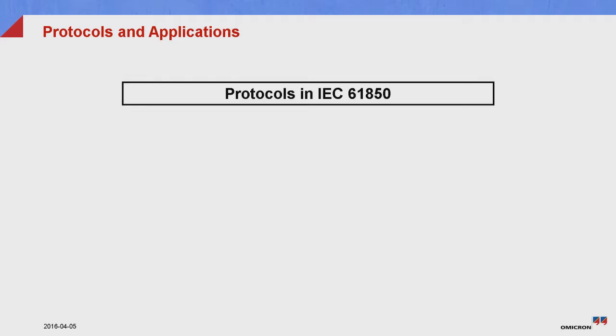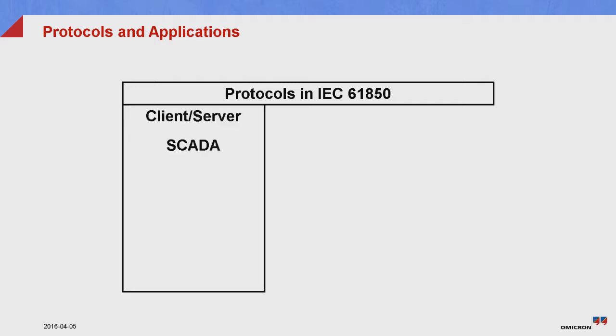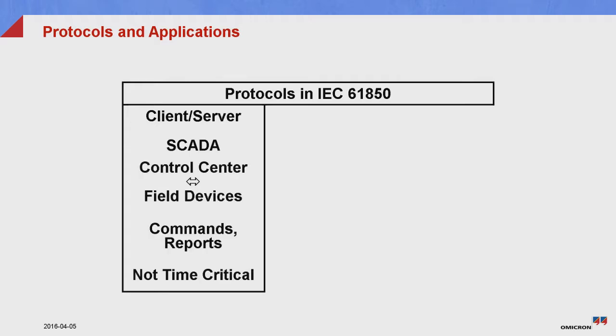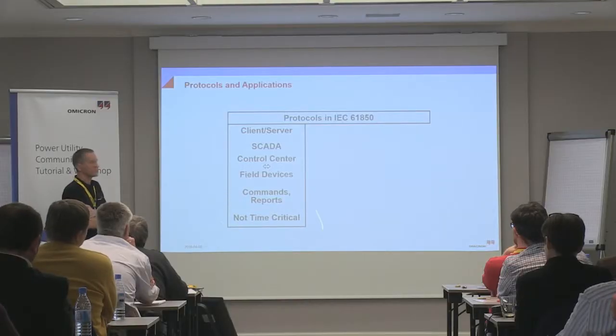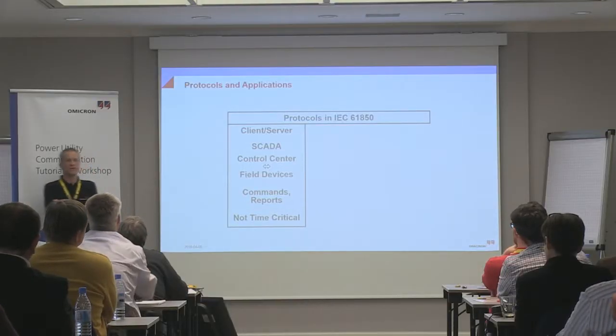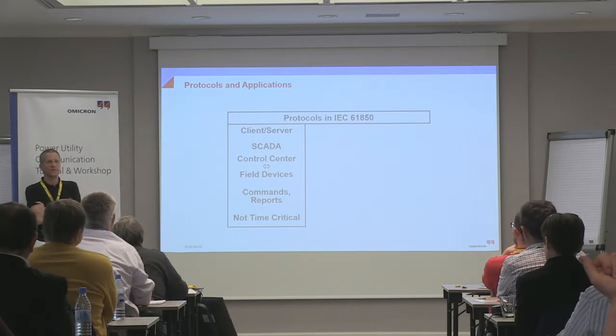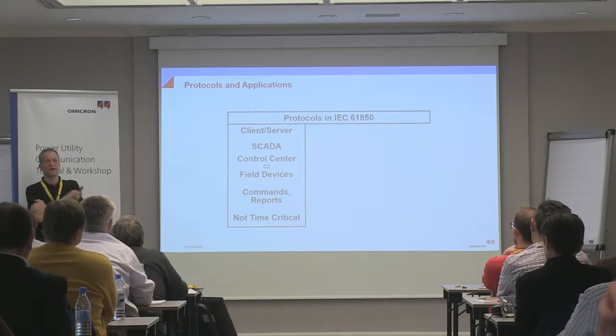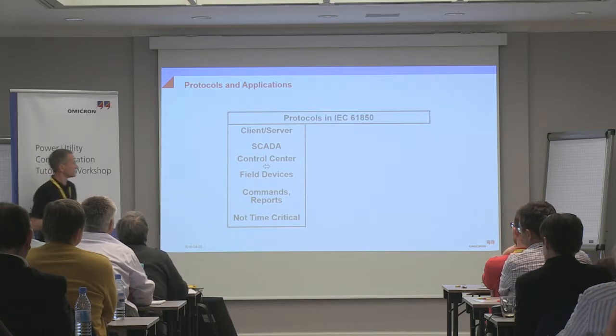Another picture that says something similar: the client-server protocol that we have here for SCADA purposes is something that I would call not time critical. What does not time critical mean? We don't care about 10 or 50 or 100 milliseconds. It's good that we have an adequate response for the operators in the control centers.